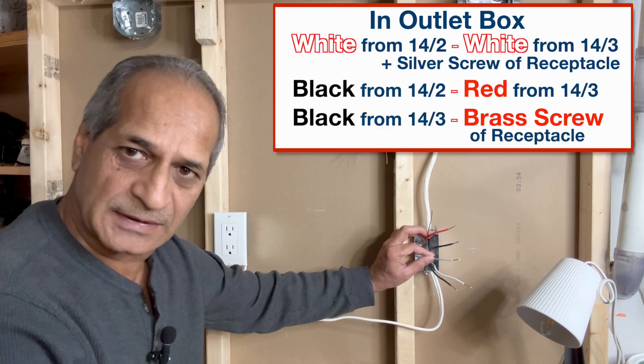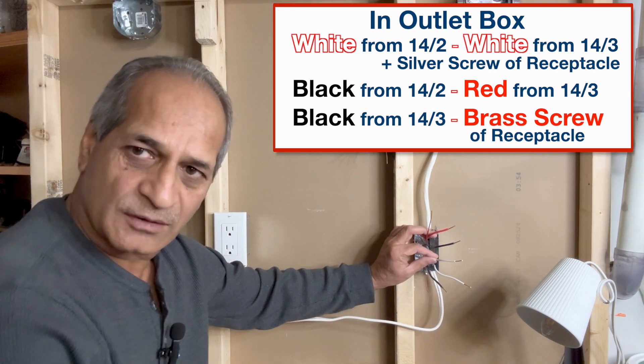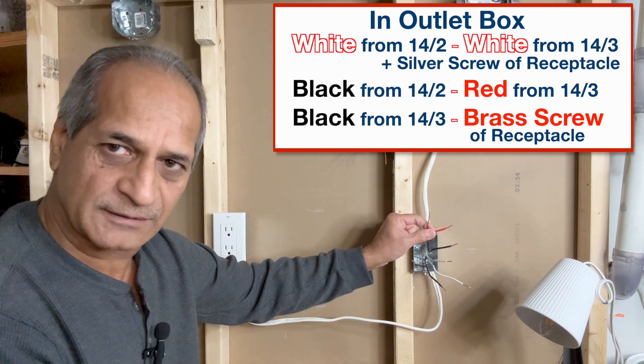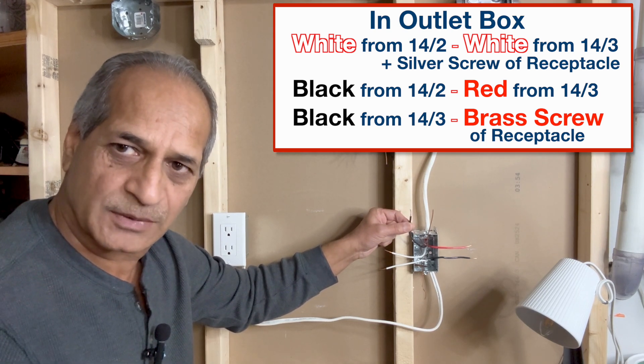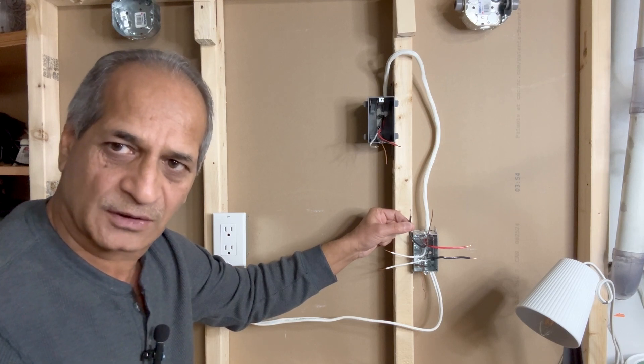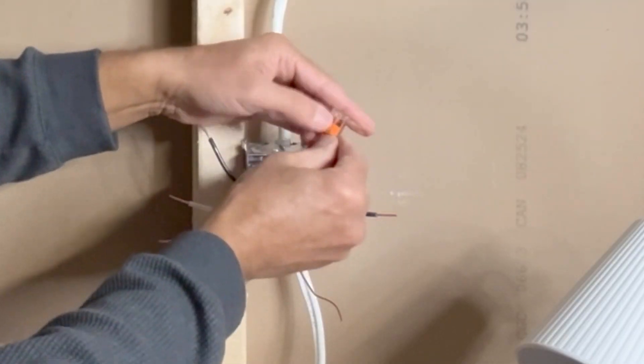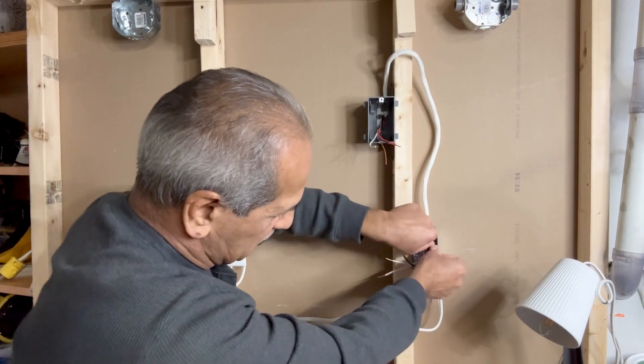The white wire from the 14-2 wire is connected to the white wire of the 14-3 wire and is also connected to one of the silver screws of the receptacle. The black wire from the 14-2 wire is connected to the red wire of the 14-3 wire. This black wire from the 14-3 wire is connected to one of the brass terminals of the receptacle and it will bring power in only when the switch is turned on. I will use a 2-pin Wago lever nut connector to connect the black and red wires. Push these two wires all the way inside the box.